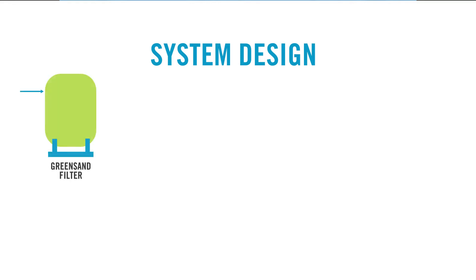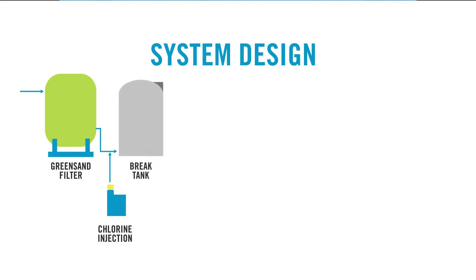Now we'll focus on the system design. The water from the well first entered a green sand filter for the removal of metals. After the green sand filter, there was a chlorine injection, which combated the biofouling that the site had experienced in their break tank. After the break tank, there was an SBS injection to reduce the chlorine, protecting the RO from oxidation damage.